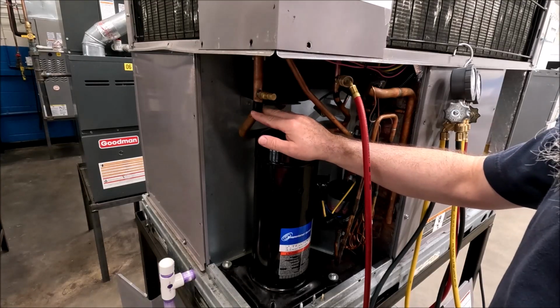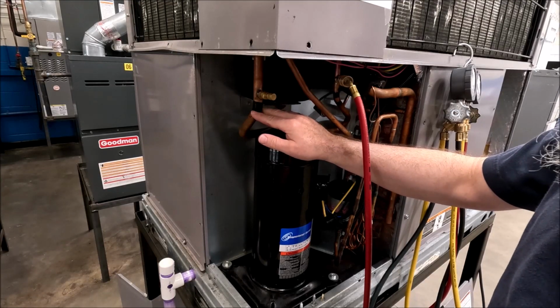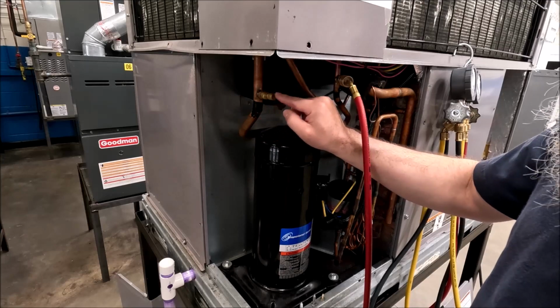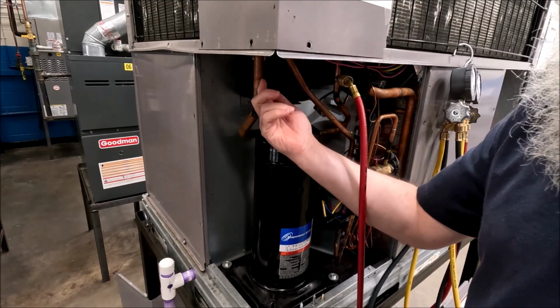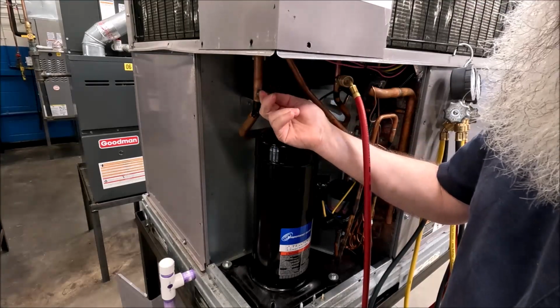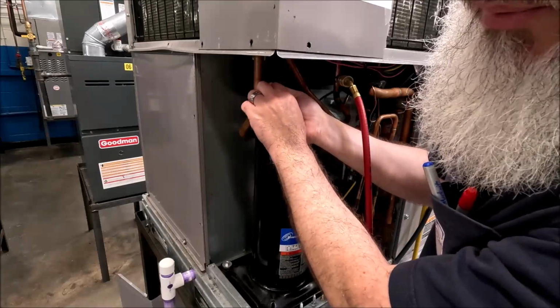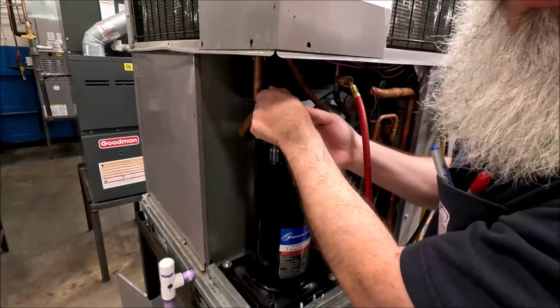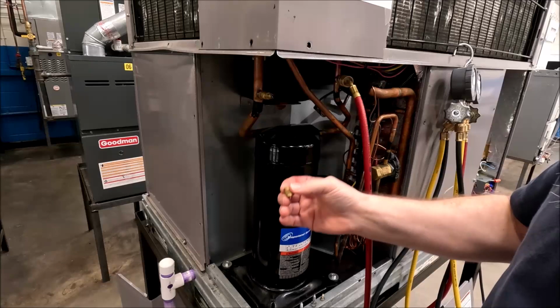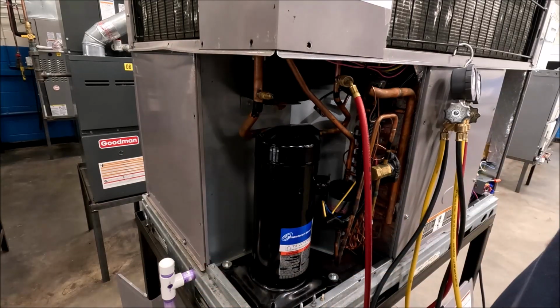All right, this is that low pressure, low temperature vapor. It's going to be superheated, and they give me an access point right there before it goes in the compressor. So if it isn't superheated here, you really don't have a whole lot of room before you put liquid in the compressor. All right, once again, brass cap, and we're going to make sure that we have an O-ring in it.